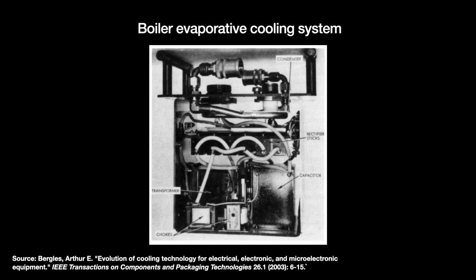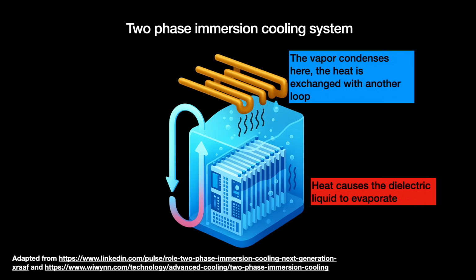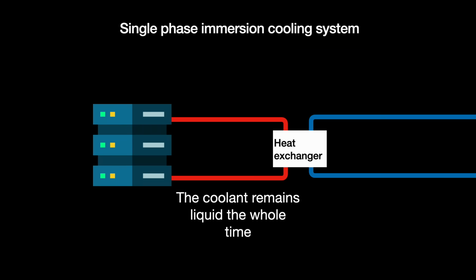One setup sprayed liquid onto the tubes. Other setups submerged the electronics in pools, boiling off the liquid. These type setups, where the coolant transitions between liquid and gas, are today called two-phase immersion. The liquid vaporizes, hits a condenser to release its heat, and then turns back into a liquid. By contrast, a cooling system where a liquid coolant remains liquid the whole time, its heat offloaded to a second water loop or something, is a one-phase immersion system.